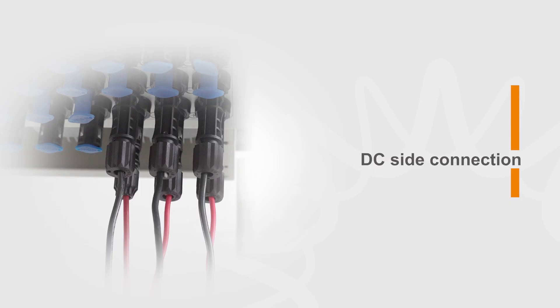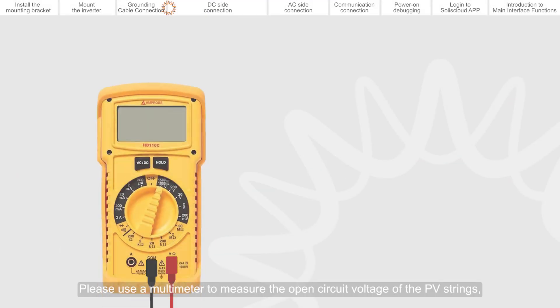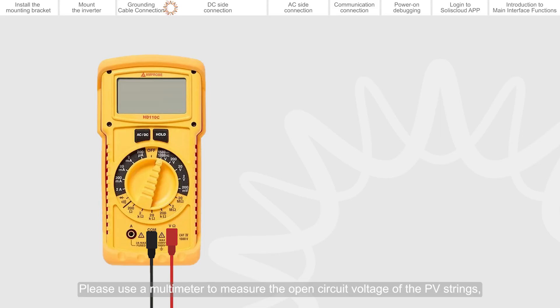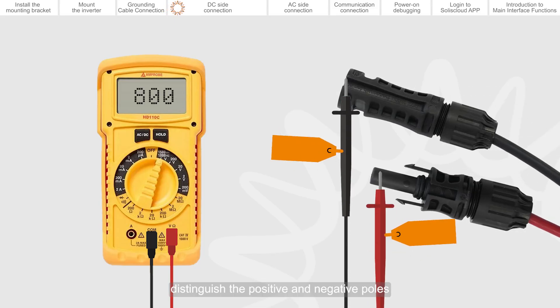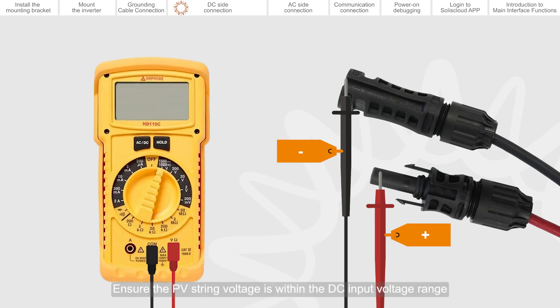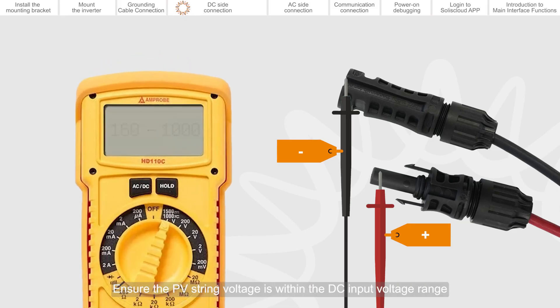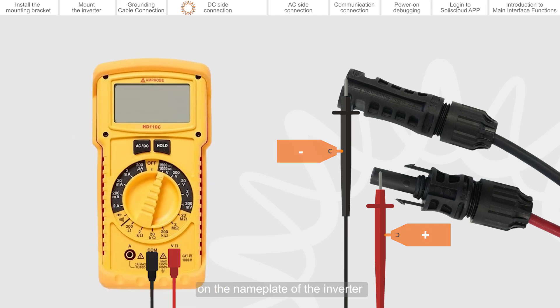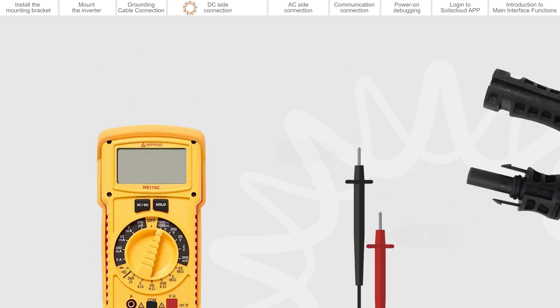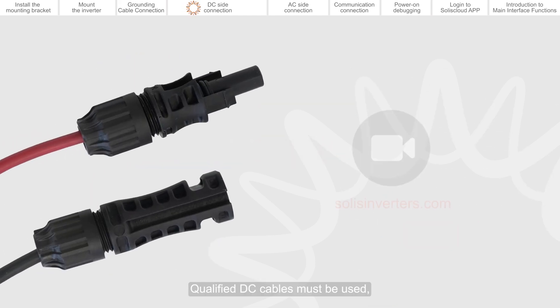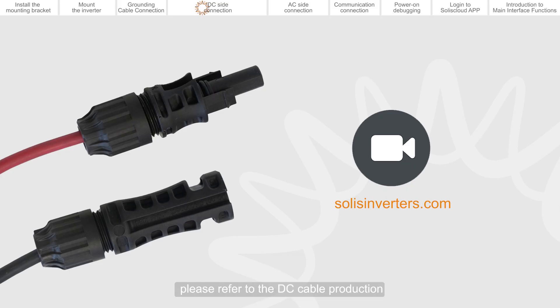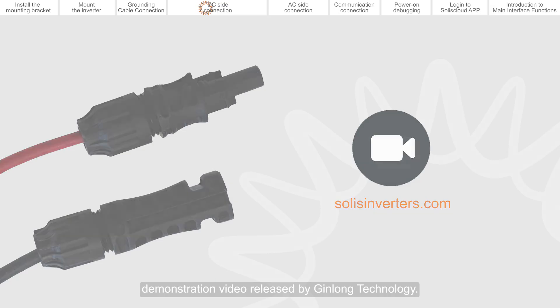DC side connection. Please use a multimeter to measure the open circuit voltage of the PV strings. Distinguish the positive and negative poles. Ensure the PV string voltage is within the DC input voltage range on the nameplate of the inverter. Qualified DC cables must be used. If you want to know how to make DC cables, please refer to the DC cable production demonstration video released by Ginlong Technology.